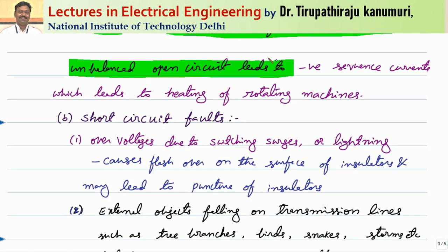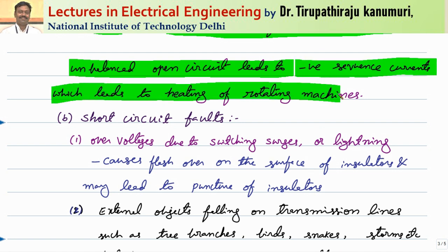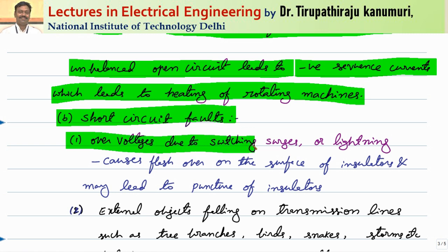Line to line, line to ground, or double line to ground faults result in different currents in different phases, leading to the same type of damaging effects in machines. Unbalanced open circuit leads to negative sequence currents, which leads to heating of rotating machines. Short circuit faults can be caused by over-voltages due to switching surges or lightning — as already discussed in traveling waves.